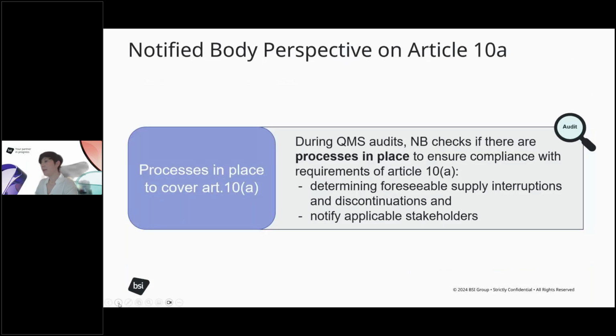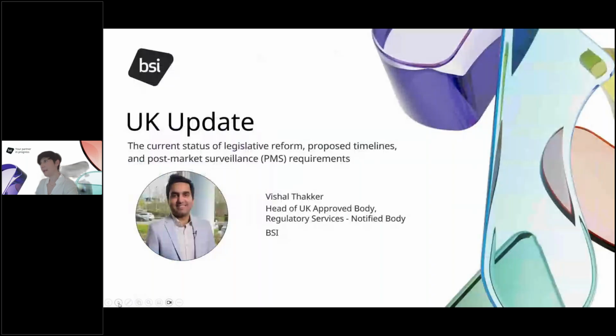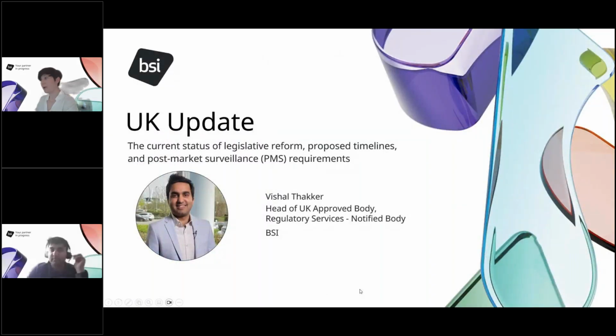So, although the notified body involvement in the notification chain is limited, our involvement as notified body will be to check that the manufacturer has the processes in place to cover those requirements of Article 10A. So during the QMS audits, the notified body will check if there are processes in place to ensure compliance with the requirements of Article 10A. And in particular, we will be checking for processes determining foreseeable supply interruptions and discontinuation, and also for processes on the notification of applicable stakeholders. And these are the three elements, and now I will hand it over to Vishal.